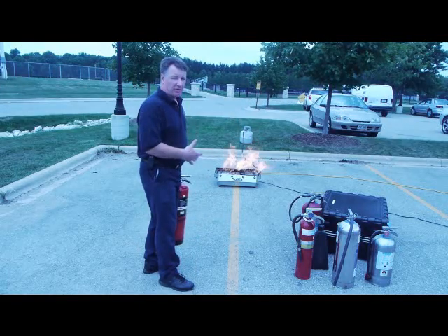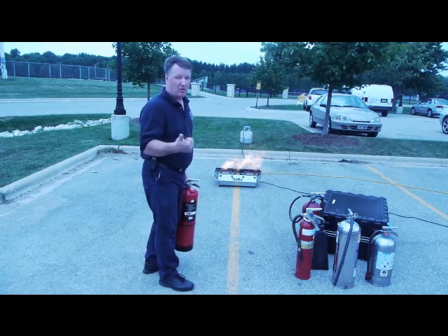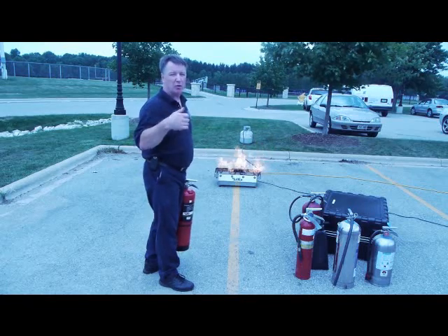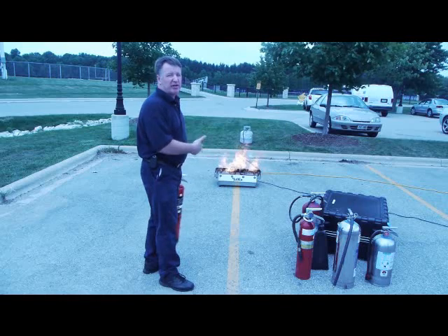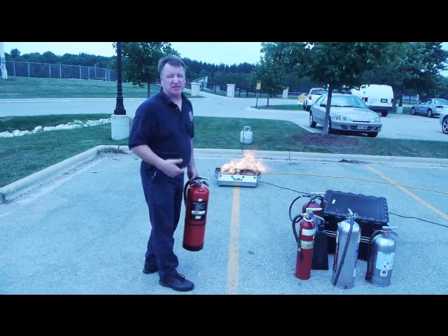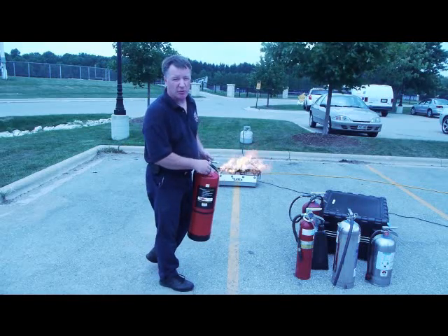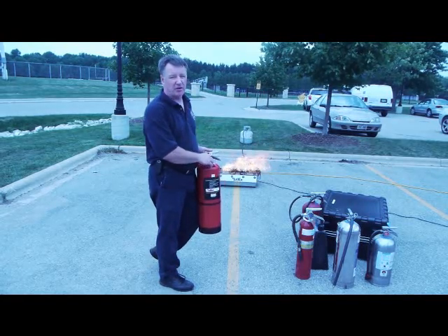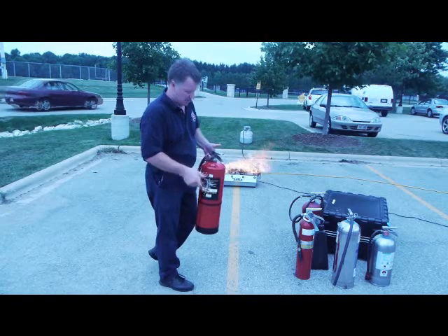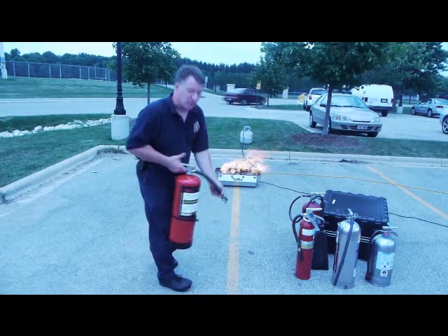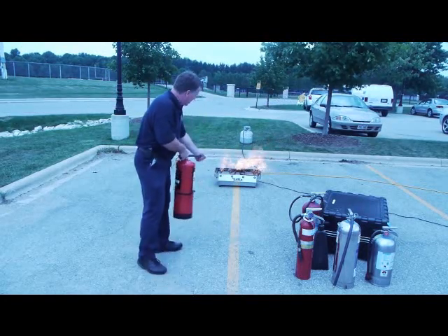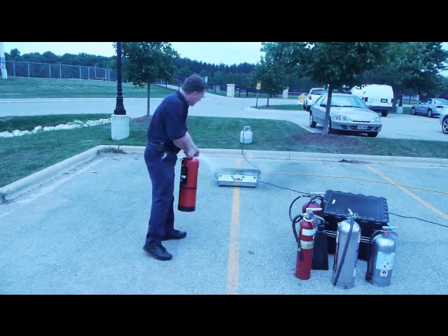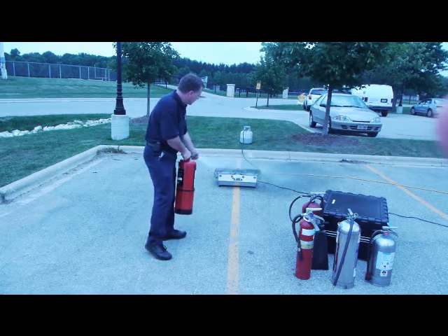So I discover fire. I need to call 911, tell somebody to call 911, rescue anybody in immediate danger. I know where my extinguishers are because I've been practicing, I've been looking where they are. I get my extinguisher, I know it's going to work for the type of fire I've got. I pull the pin, I remove the nozzle from the holder, I aim it, I squeeze, and I sweep back and forth.